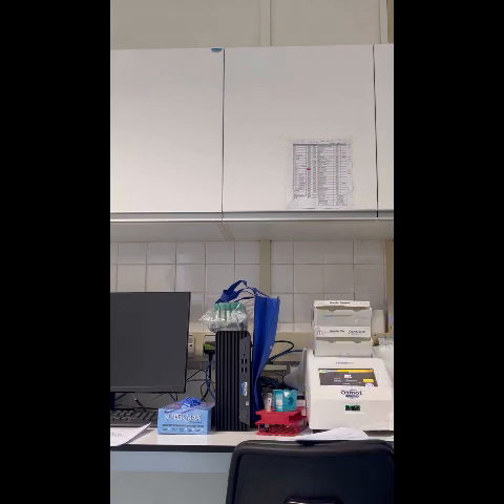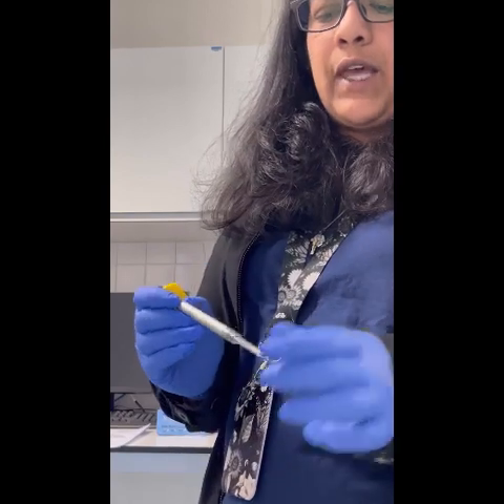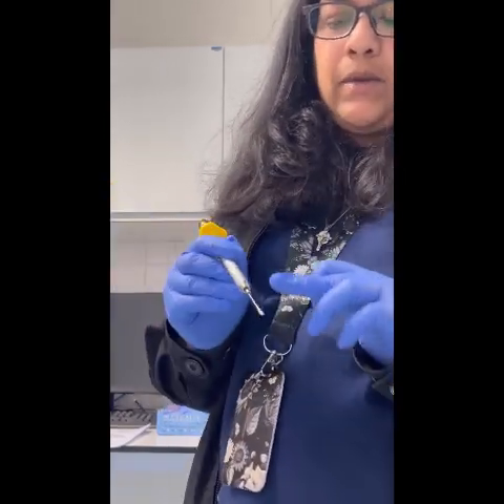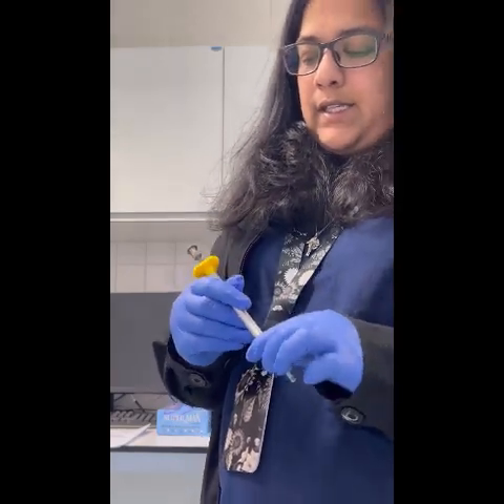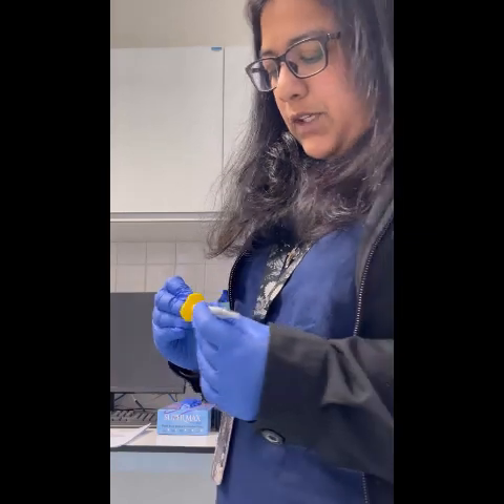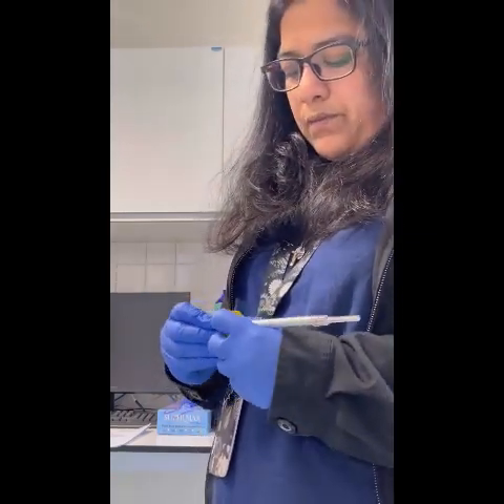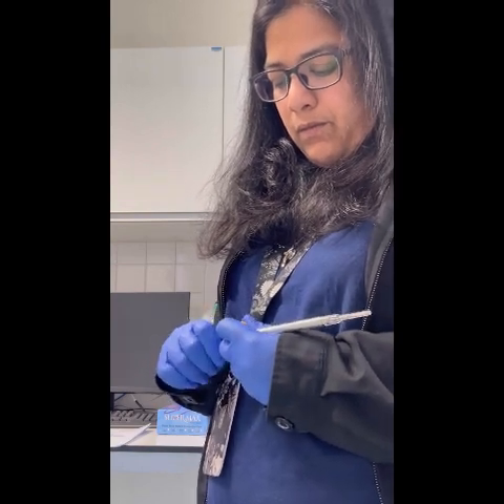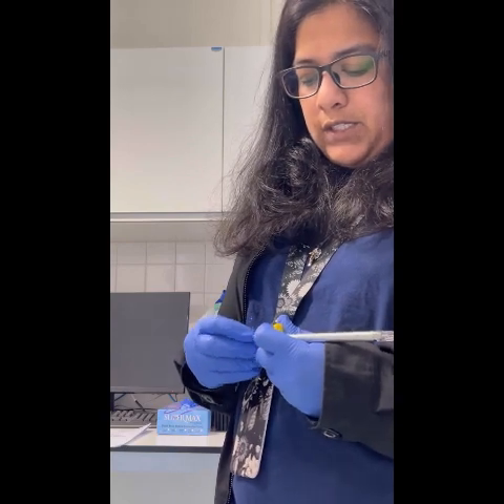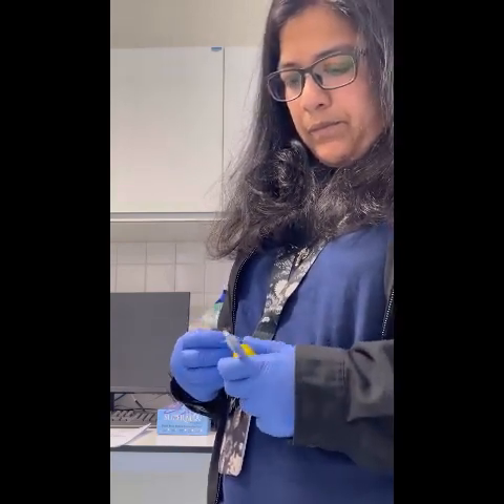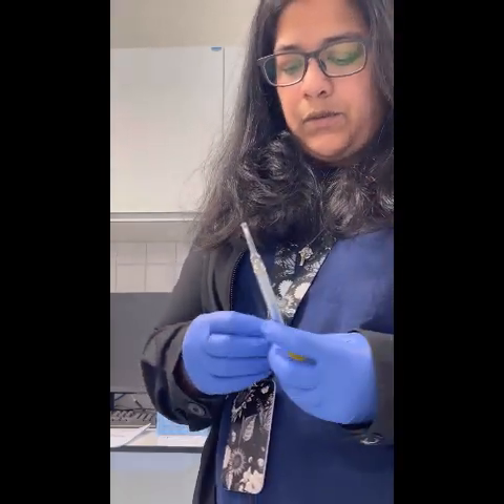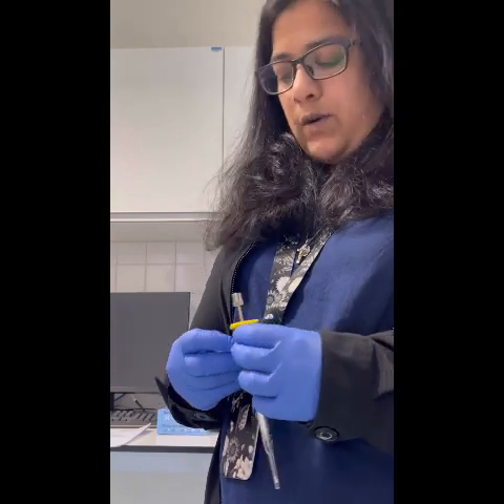Okay. As of now, we don't have any calibration for this osmometer. The calibration is done by the manufacturer themselves, but we do have calibration for this sampler, which we have to do every time we change the plunger. So this is the plunger, and then this is the needle calibrator. What we have to do is remove this, and we have to put it into this hole and spin anti-clockwise.